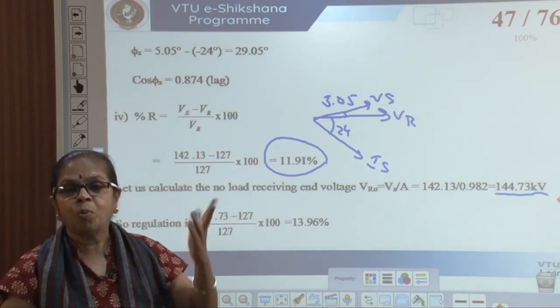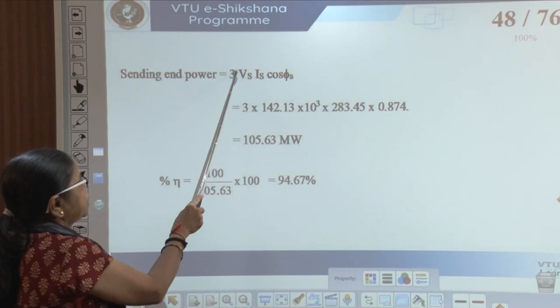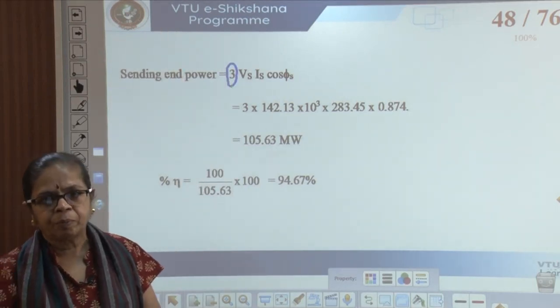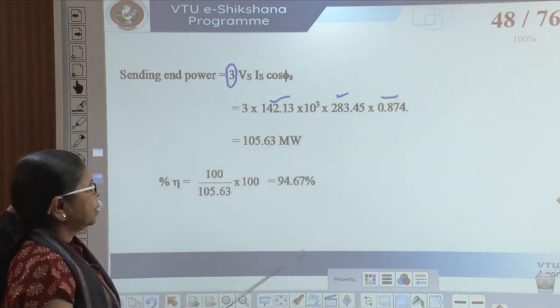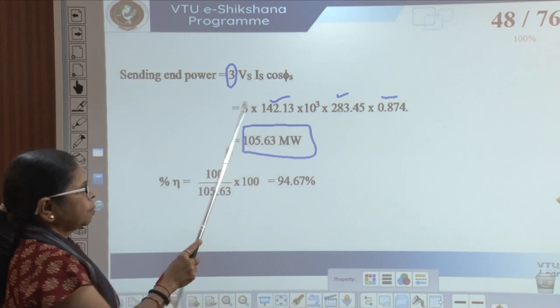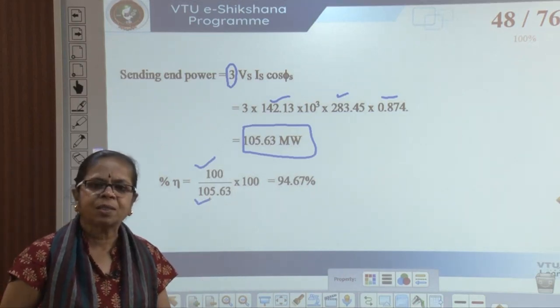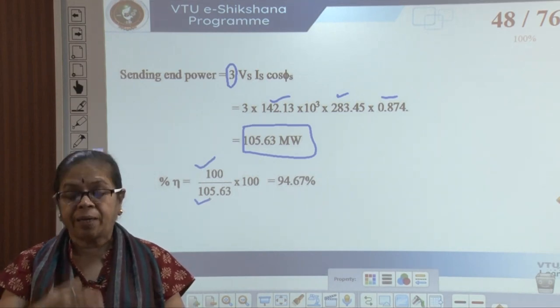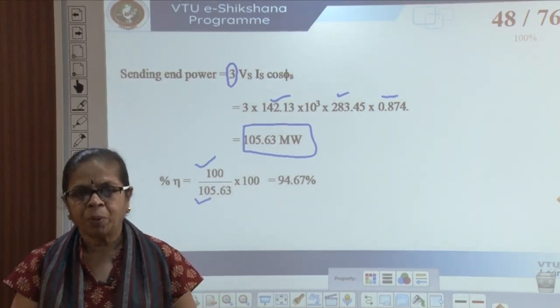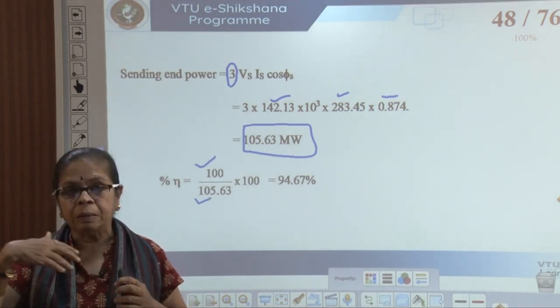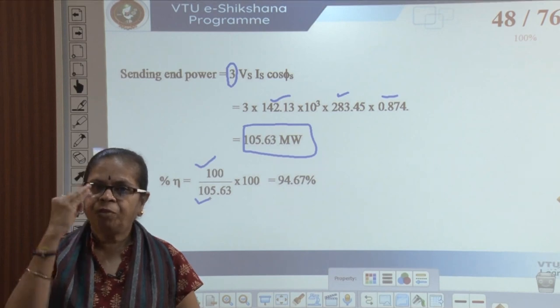Sending end power is 3·Vs·Is·cos(φs). Considering three-phase power, I get 105.63 MW. Receiving end power is 100 MW, so efficiency is 94.67%. For short lines efficiency was very high — 98, 99 — but now it has come down. Not as low as 60 or 70, but around 95%. As the line length becomes longer, regulation becomes poorer and efficiency also decreases.